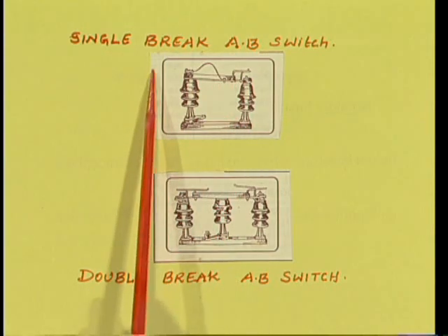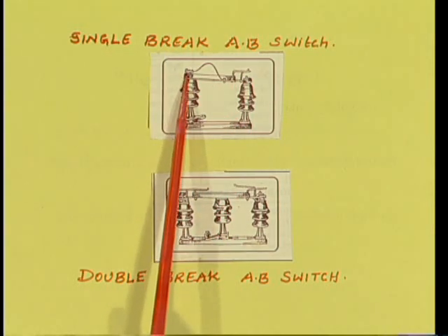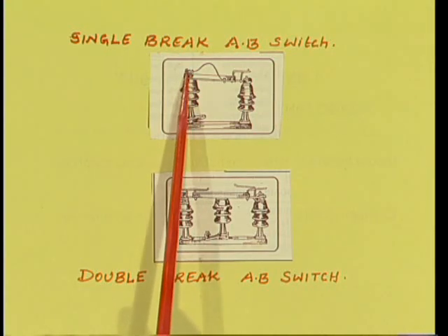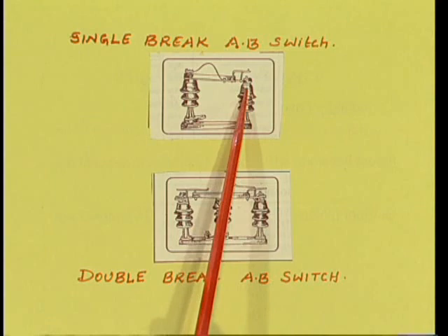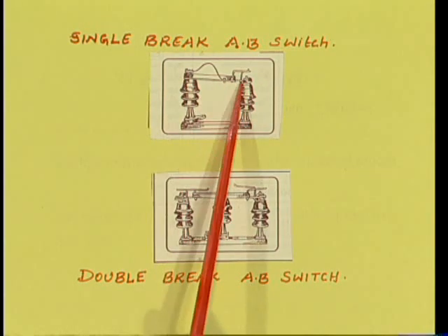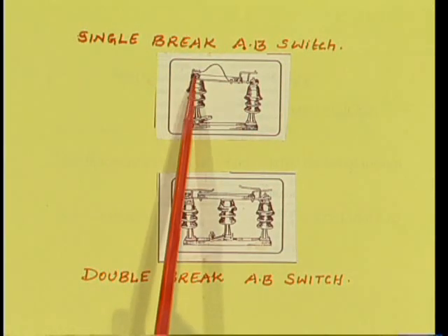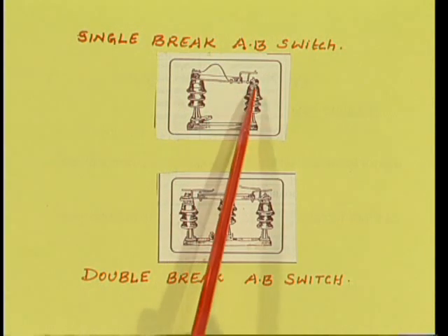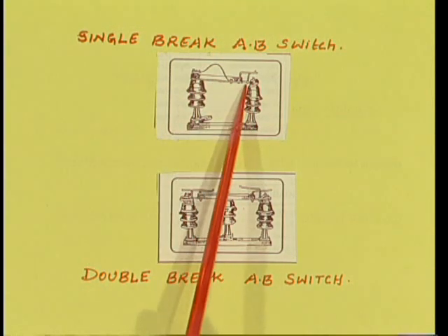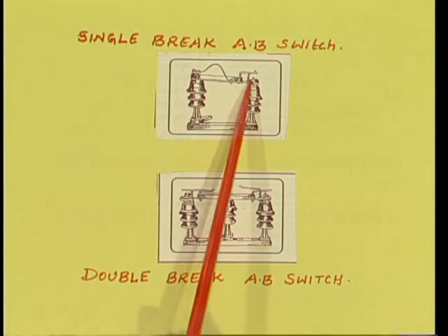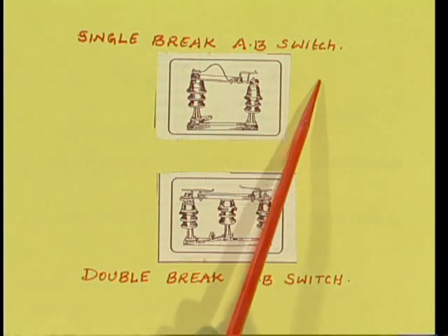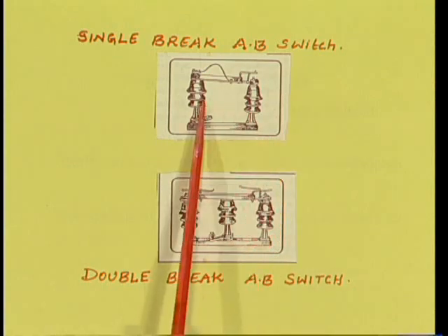other insulator, and we receive the power at one of the insulators, and on top of the insulator you will have a metallic contact, and the other insulator also will have a metallic contact. To connect these two metallic contacts, there is an operating rod. So you give the supply to one of the metallic terminals, and when the operating rod is closed in between these two, then the supply goes from one rod to another rod, and from here it is connected to a load part. And this is a single pole.